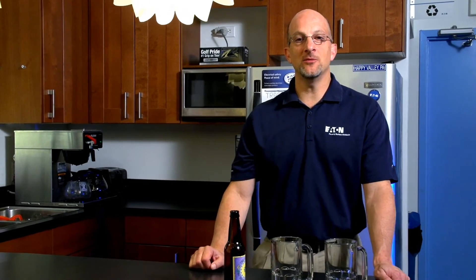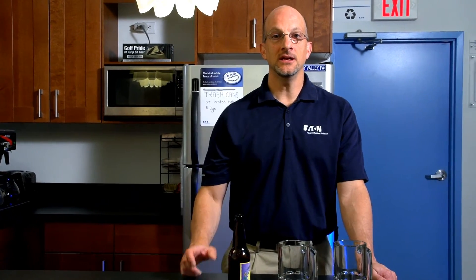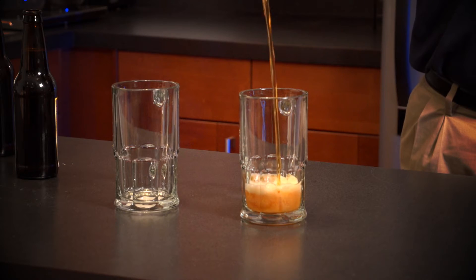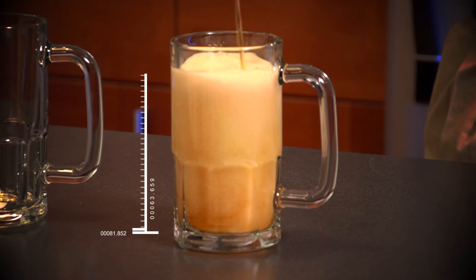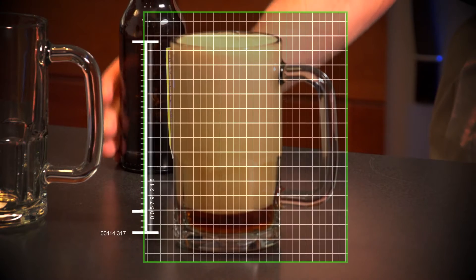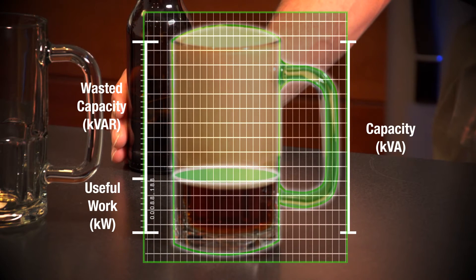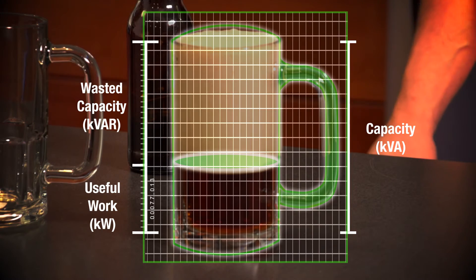One of the most common ways to explain how reactive power takes up system capacity is the beer analogy. If you filled a mug with beer and weren't careful, you could fill up the glass with foam. With the mug, the capacity is fixed and measured in ounces; with the transformer, the capacity is fixed and measured in KVA. The foam represents reactive power taking up part of the capacity, while the beer represents the kilowatts — the desired part.